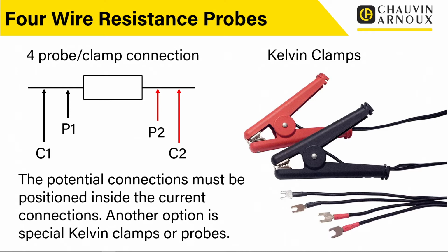Now, when we are measuring inside, just be aware, we talked about the length, and the measurement positioning of the probes. When you're positioning P1 and P2, that's where it's going to measure in between. So if you're worried about the length, say you were trying to measure the resistance of a cable, it's the distance between P1 and P2 that you're actually measuring the resistance of, not the position of C1 or C2. So you might put C1 and C2 a metre apart, put P1 and P2 in the middle and think you're measuring a metre, you're not. So put your C1 and C2 either side, and the distance between P1 and P2 is the actual resistance you're measuring. So where you're clipping those on really matters when you're doing this, so it's really important.